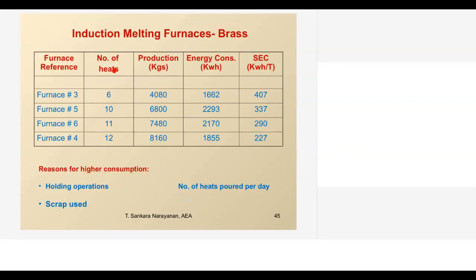So this is a case of an induction melting furnace where brass is melted. This plant has more than 10 or 12 induction furnaces, with a furnace platform. Daily they run at least 10 or 11 furnaces. So when we did the audit, we took an analysis: when the number of heats they are taking is lower, what is the specific energy? When the number of heats is increased, how does the specific energy vary?